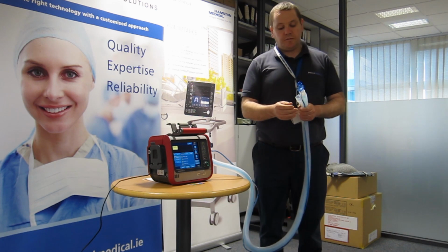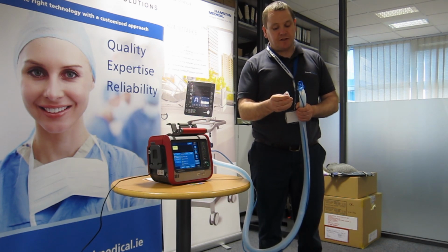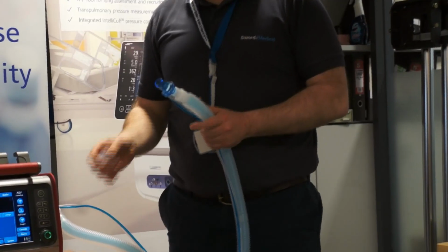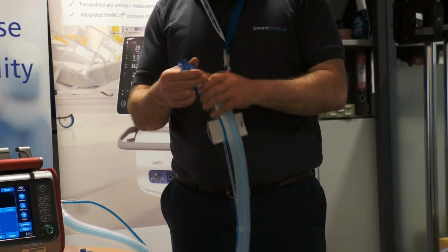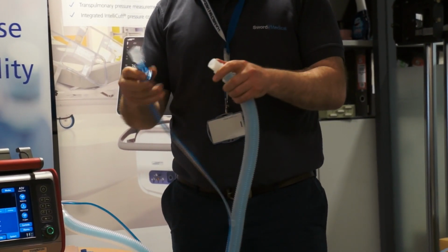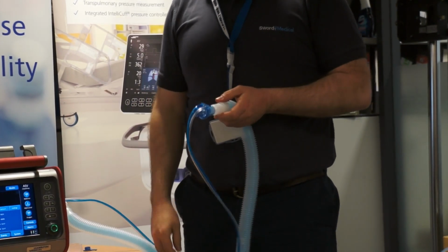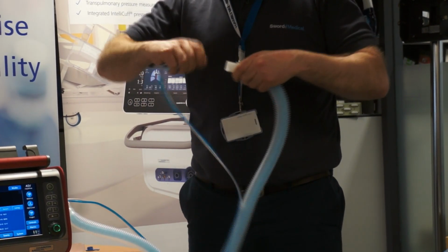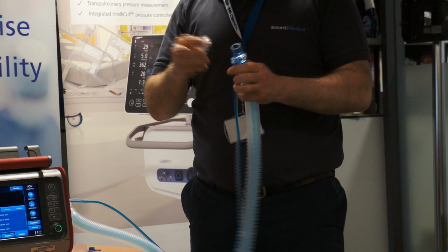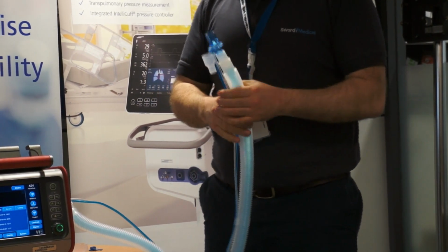So each circuit comes with a sizing adapter that allows me to turn the flow sensor for calibration. So the ventilator is going to prompt me to turn the flow sensor, and I put in my sizing adapter on top, and then I can turn the sensor around for calibration in this direction, and then I'm going to turn it back again for calibration in the opposite direction. So I'm going to show you how that looks on the ventilator.